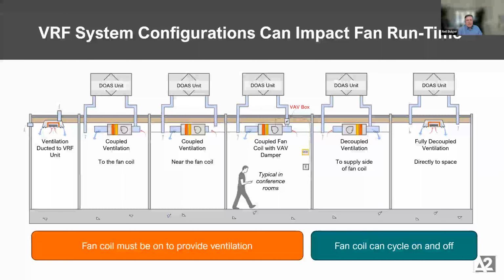A lot of it comes down to engineers' risk tolerance, which is really the challenge I've hit. In a lot of jobs where I am not the engineer of record, which is most, it's really about ensuring that the engineer of record, and even the client, understand that you can make a comfortable decoupled system work. A lot of the jobs I've seen will just default to ducted to the back of the unit or ducted to a plenum. And it's a little driven by cost because it is cheaper. You have fewer holes to put in the ceiling. You also potentially have less duct because you're just ducting to a plenum. But then the pushback I often receive is that if we don't do this, we might end up with a risk. We might dump cold air all over people. And what if they're uncomfortable? I don't want to do it. So that's been a big challenge.